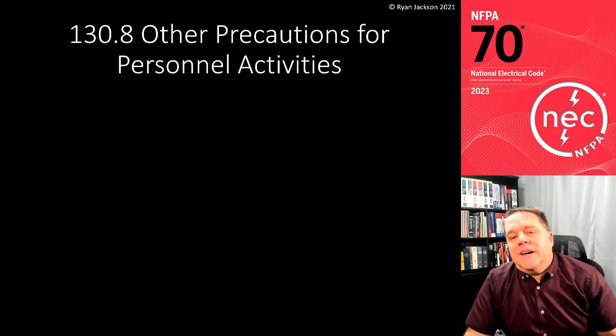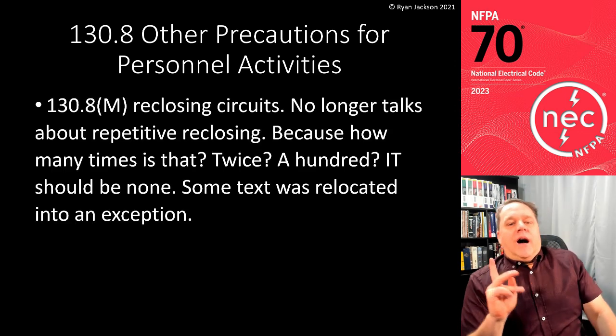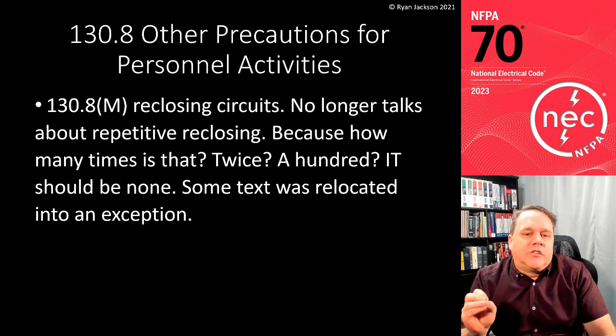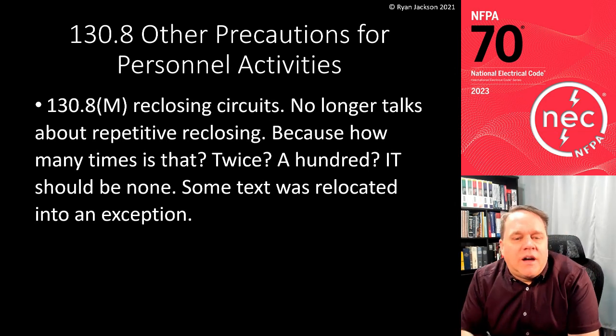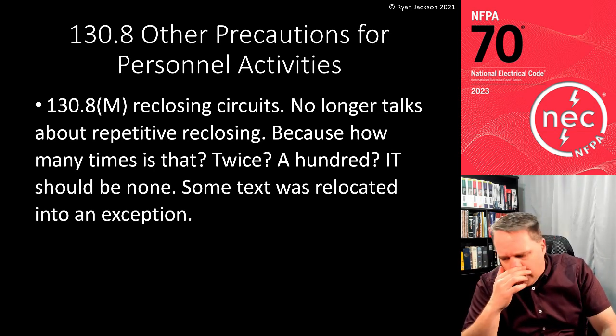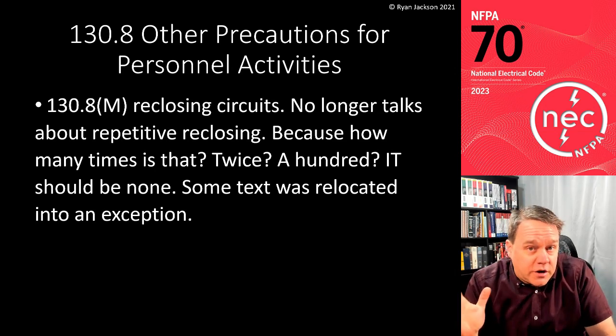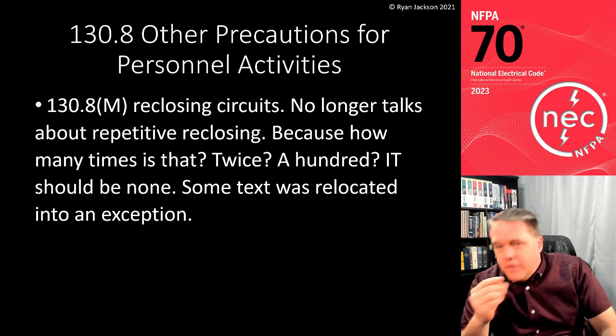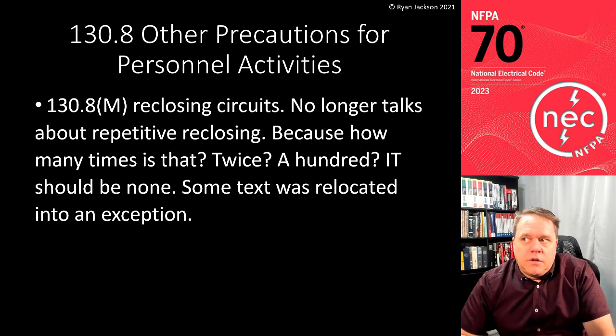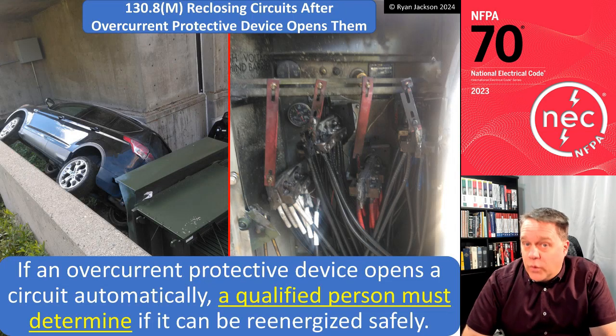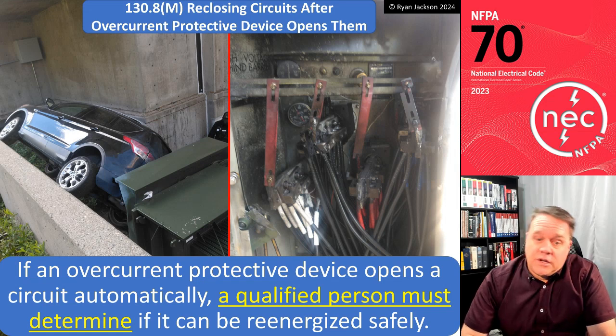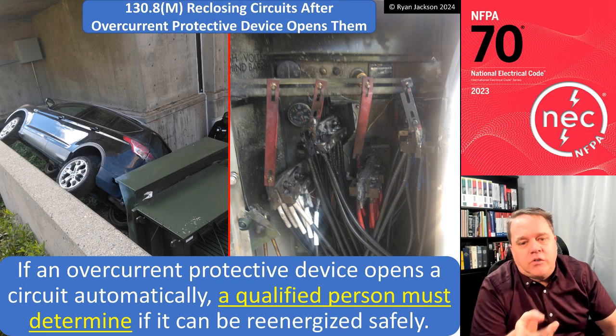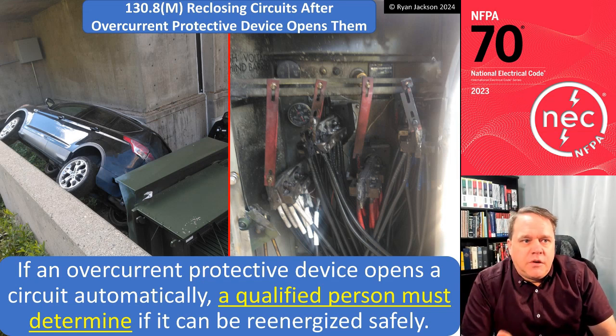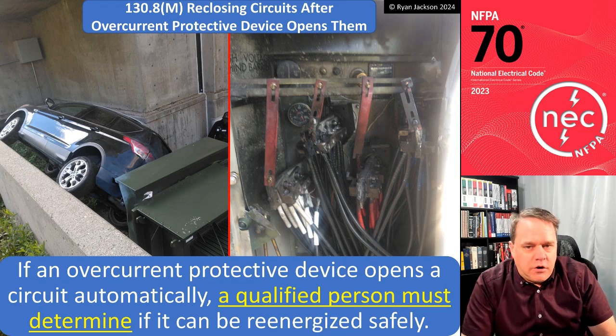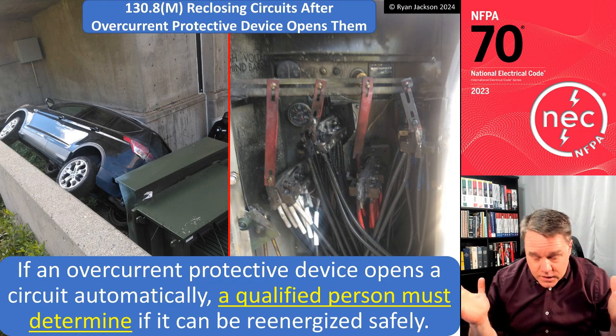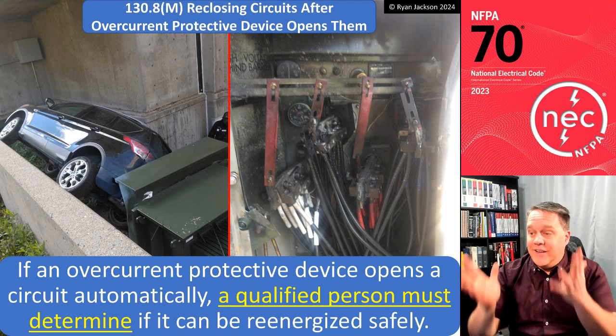All right, 130.8, other precautions for personnel activities. Item M, reclosing circuits. No longer talks about repetitive reclosing, because how many times is that? Makes sense. So what it said before is if a circuit breaker actuates, right, an overcurrent device opens automatically, then don't repetitively reclose it. Okay, well, what does repetitive reclosing mean? Is that once, or is that 100 times, or is it twice? And now it's actually more clear. It says if an overcurrent protective device opens a circuit automatically, then a qualified person must determine why it happened and if it can be re-energized safely. All right. Never underestimate the abilities of humans, right? I mean, I have no idea how this happened.